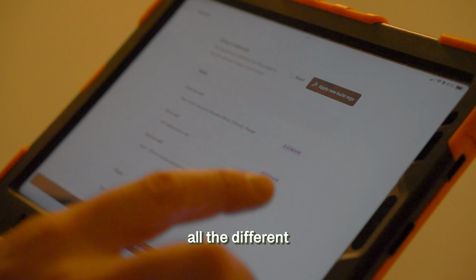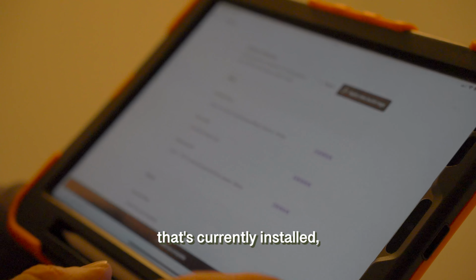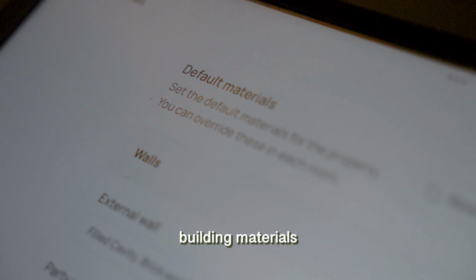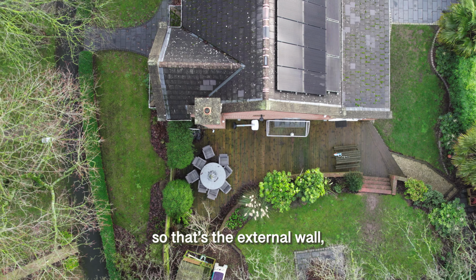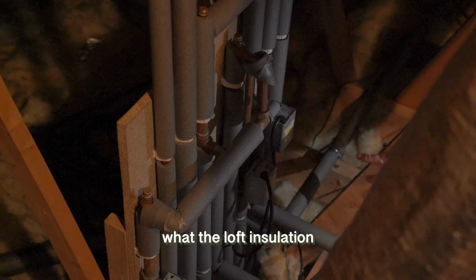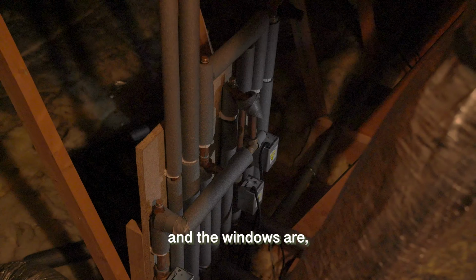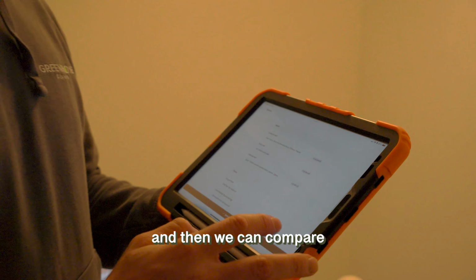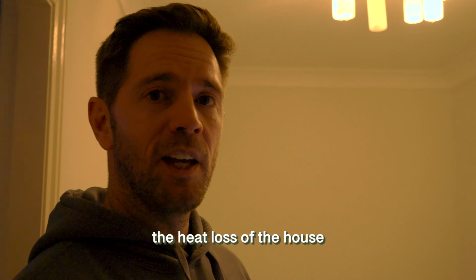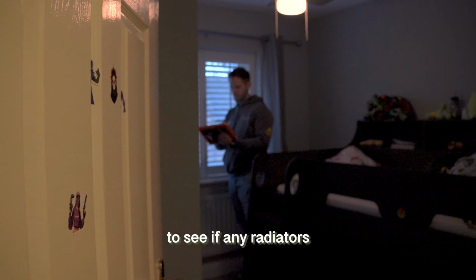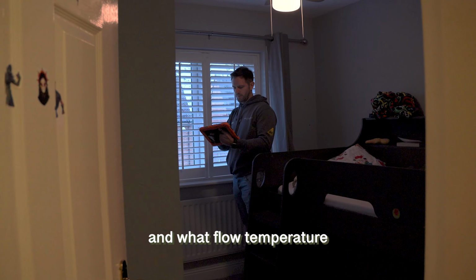Now that we've selected all the different radiator sizes that are currently installed, we can input all the building materials. So that's the external wall, what the makeup of the external wall is, what the loft insulation and what the floor and the windows are, and then we can compare the heat loss of the house against the current radiators to see if any radiators need changing and what flow temperature those radiators will work at.